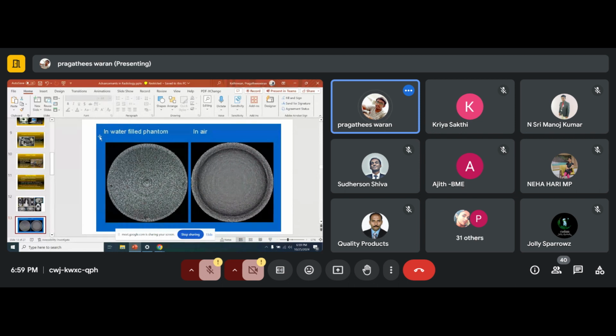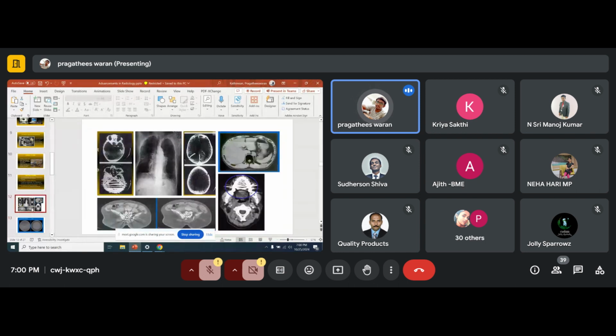This is a water-filled phantom. Under CT scan, if you fill water in a cylinder, it is seen like this. And this is an air calibration without any phantom. If you expose normally, the images will be like this. So first we take a scan with this phantom, then based on this, we start troubleshooting what kind of artifact it is. If it is this kind of artifact, then we check the power and all these things. For breathing artifacts, meaning motion artifacts, if you detect them, we check accordingly.